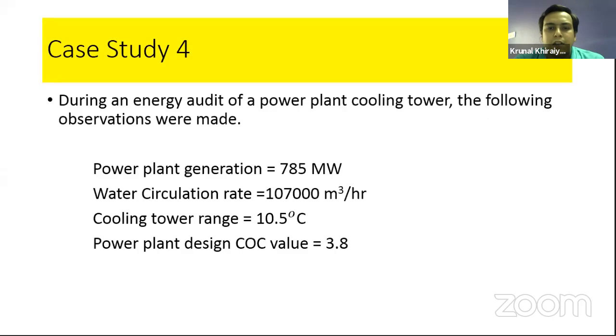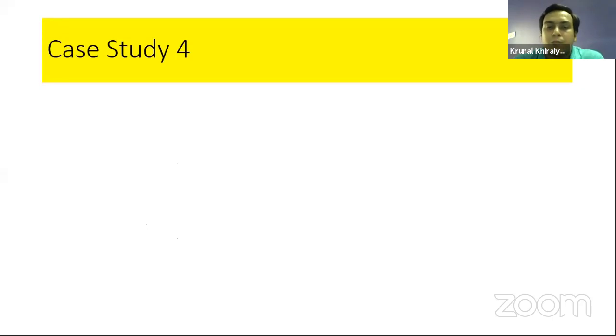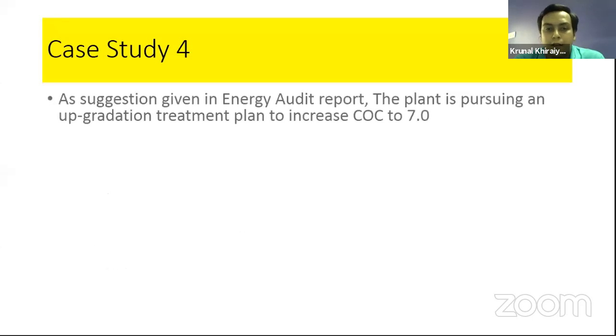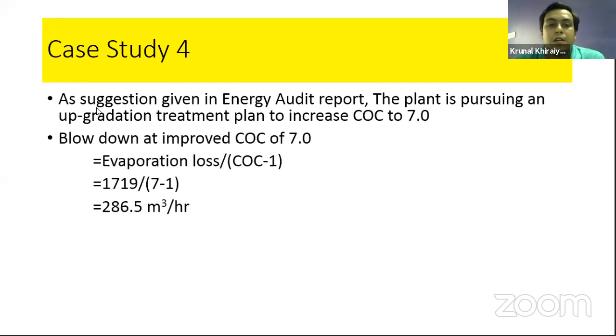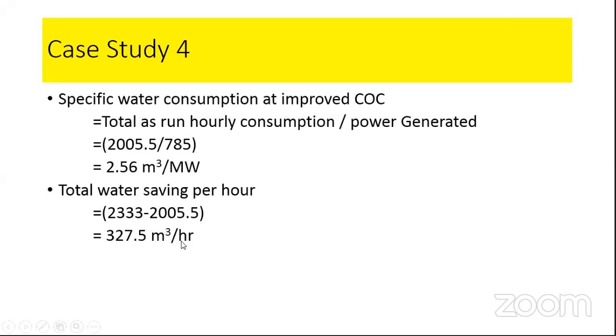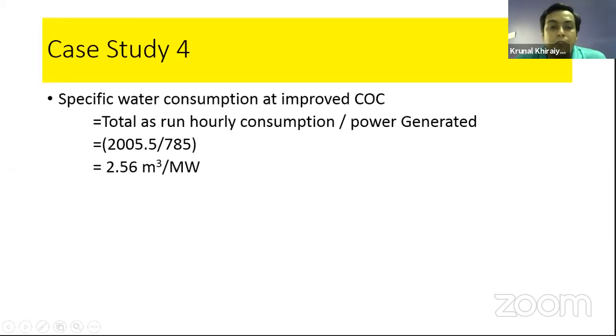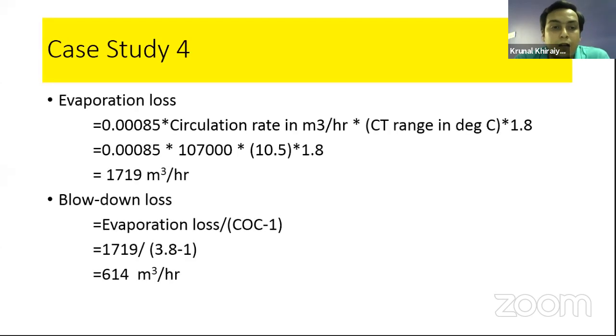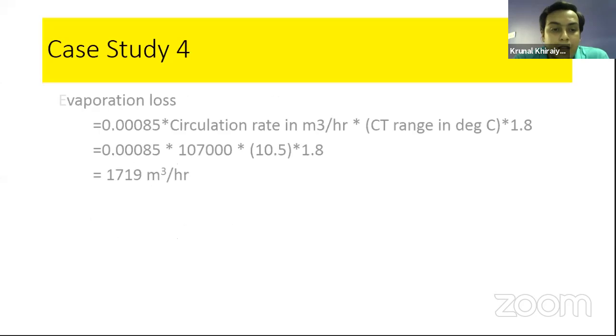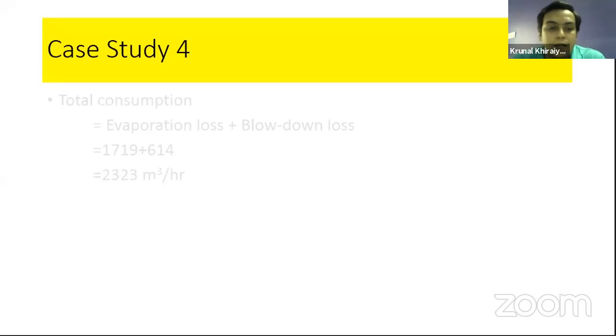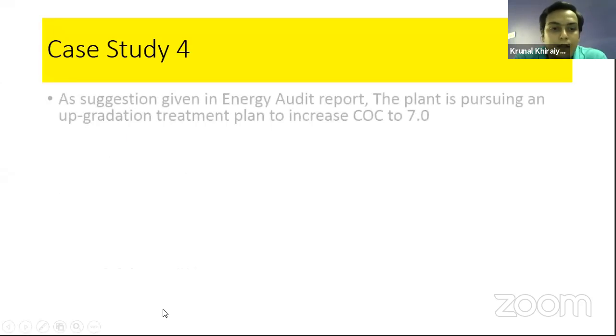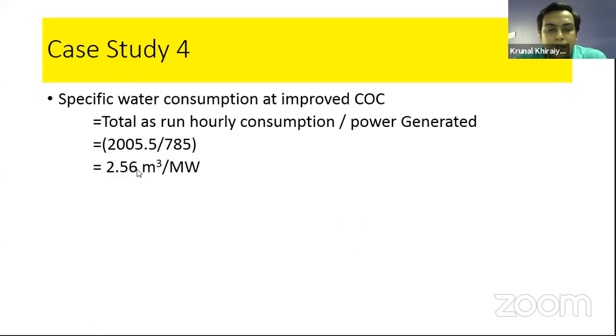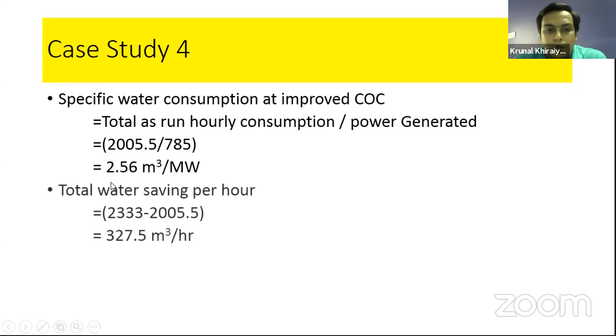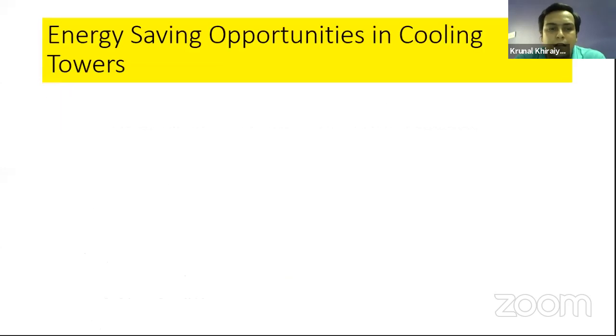So in this case study, we have a power plant designed on a COC of 3.8, and we suggest a COC of 7 by applying some amount of good treatment, means a water treatment plant. So this is how the savings occur, and specific water consumption is reduced over here. See, if the power plant is running with a COC of 3.8, then the specific consumption is 2.97 meter cube per megawatt. If we go with 7 COC, then specific consumption becomes 2.56. So definitely we have a saving of water. Means this case study is for water conservation practices in the cooling tower.